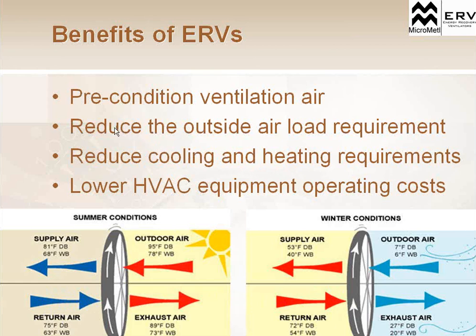Now, if we go to that second bullet point, I said we're going to reduce the outside air load requirement. Now, that's crazy. An outside air load requirement is based on the ventilation standard, correct? Well, now we're bringing in fresh air through the system and preheating and cooling it. We don't have to worry about either a 100% makeup air unit or bringing in extra ventilation and heating or cooling that through our rooftop unit. We're heating and cooling it with the energy recovery ventilator. And that's how we're reducing the cooling and heating requirement of typically, let's say, a rooftop unit.